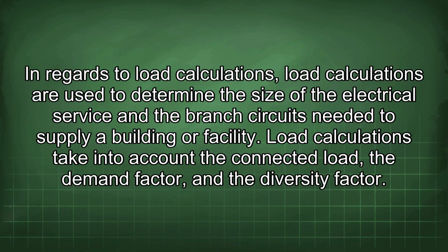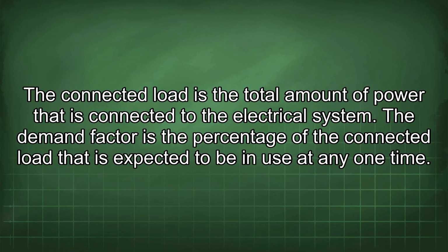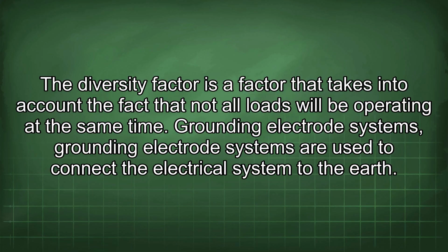In regards to load calculations, they are used to determine the size of the electrical service and the branch circuits needed to supply a building or facility. Load calculations take into account the connected load, the demand factor, and the diversity factor. The connected load is the total amount of power that is connected to the electrical system. The demand factor is the percentage of the connected load that is expected to be in use at any one time. The diversity factor is a factor that takes into account the fact that not all loads will be operating at the same time.